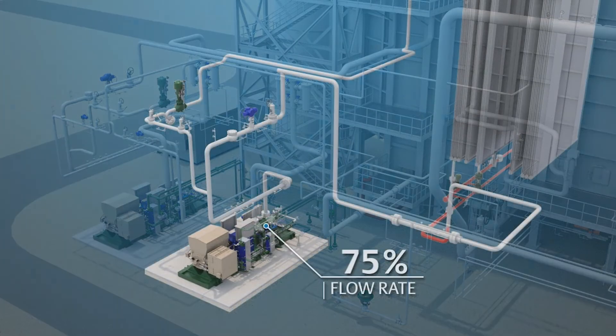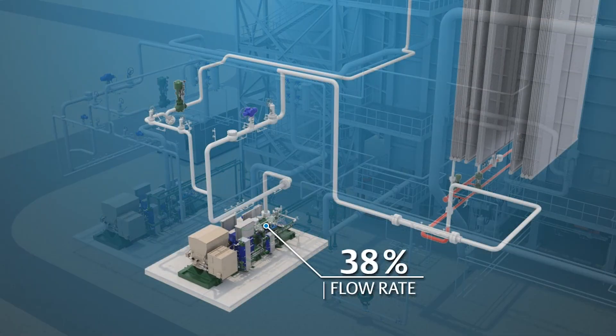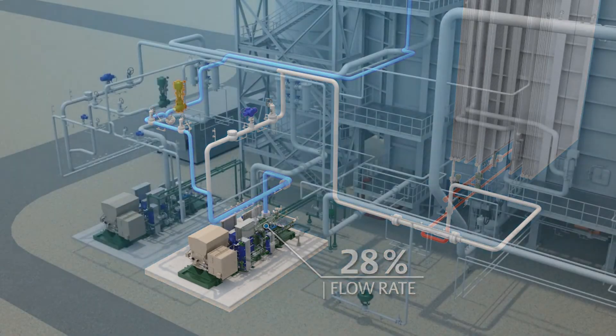When feedwater flow rate is reduced below 30%, the boiler feedwater pump recirculation valve opens to maintain required cooling flow through the pump.